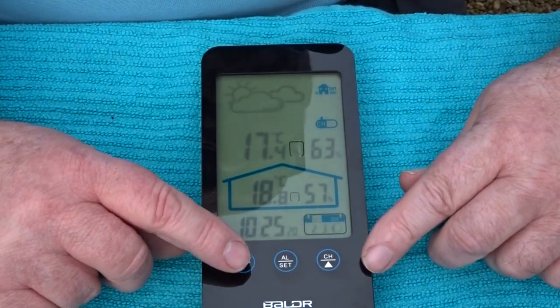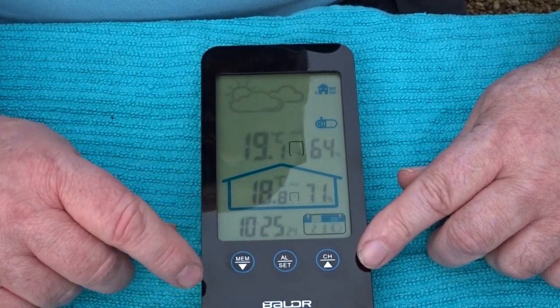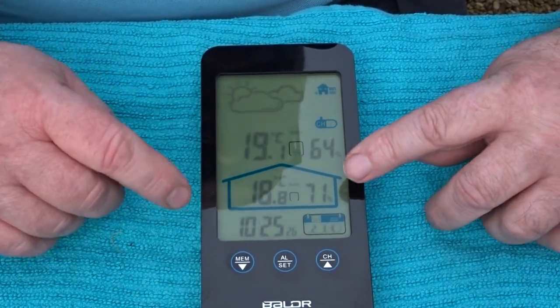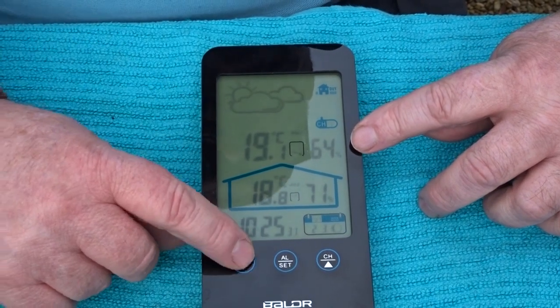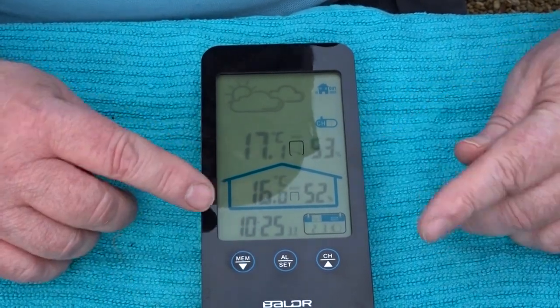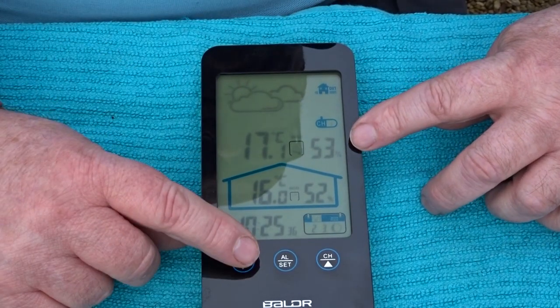When you press MEM you get the memory max/min. The maximum indoors has been 18.8°C at 71% humidity, and outdoors 19.1°C at 64%. The minimum indoors was 16°C at 52%, and outdoors 17.5°C. If you press and hold the MEM button it clears the max/min readings.